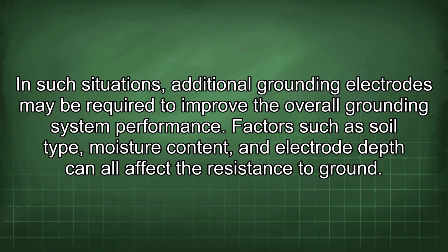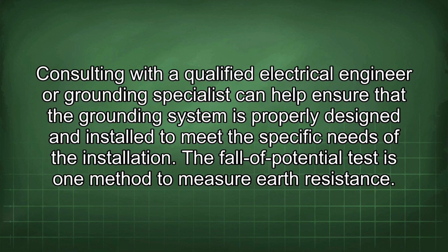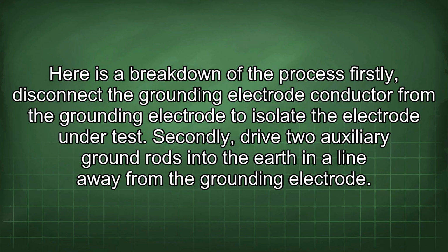Factors such as soil type, moisture content, and electrode depth can all affect the resistance to ground. Consulting with a qualified electrical engineer or grounding specialist can help ensure that the grounding system is properly designed and installed to meet the specific needs of the installation. The fall of potential test is one method to measure earth resistance. Here is a breakdown of the process.